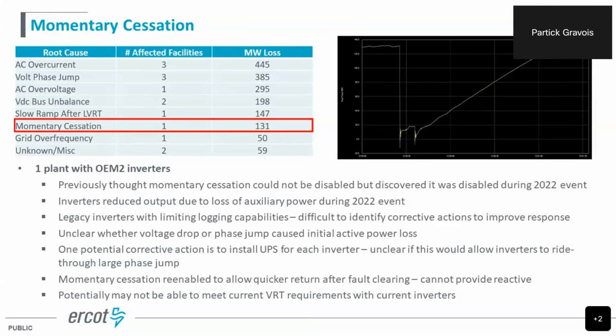So the only potential corrective action was to potentially install an uninterruptible power supply at each inverter. But even the OEM was not certain that this would fix the problem, especially for an event with a large phase jump like the Odessa events. So we're still working with this plant. It doesn't look like they're going to be able to meet our VRT requirements, our requirements to provide reactive. So this is going to be an ongoing issue. This is the plant that we're really going to have a hard time getting up to speed to meet our requirements.